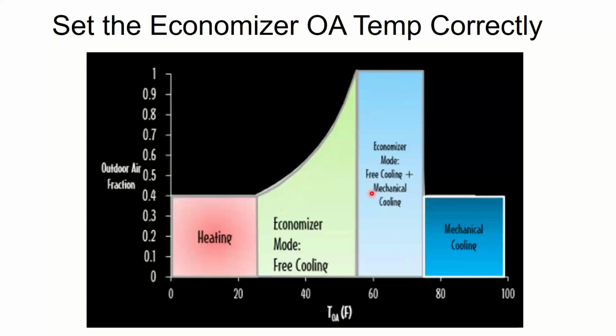That's great when I do that, and I can do it by itself or in conjunction with the compressors. I'm going to overventilate to get the free cooling, but that's okay because the ventilation air isn't bad, it's good for me. I just don't want to ventilate at 100% all the time because it's so expensive during heating and cooling. But in the middle times, I'm not really paying to heat or cool it, so let's take the free cold air and the bonus ventilation.